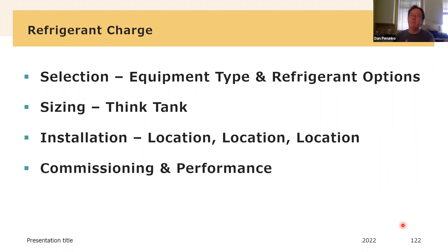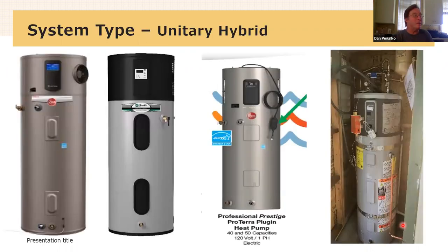I've talked a whole bunch about tons, right? And tons of air conditioning. In space heating and cooling, smaller equipment is better. In water heating, you don't get to choose how big the equipment capacity is. They're all pretty low. They don't make a lot of hot water at once, but you do get to pick how big the tank is. And that tank is the equivalent of a battery of hot water. So the bigger the tank is, the better off you are. And then that location piece that I just mentioned is about access to available ambient air. And then we have a little commissioning stuff we can look at. There's not a lot, actually. These are kind of simple once you get your head wrapped around where you're going to put it.